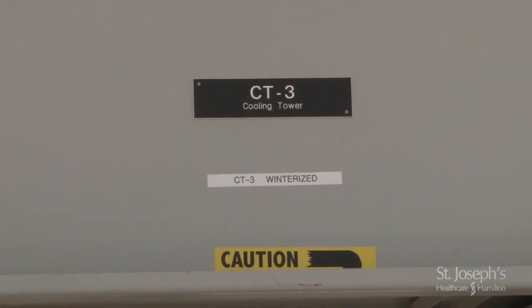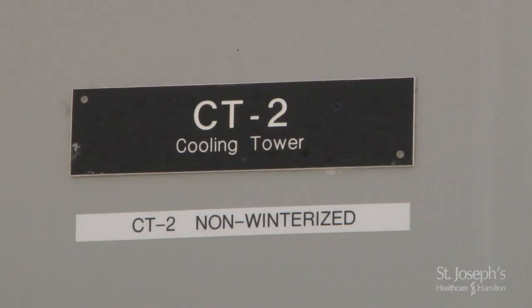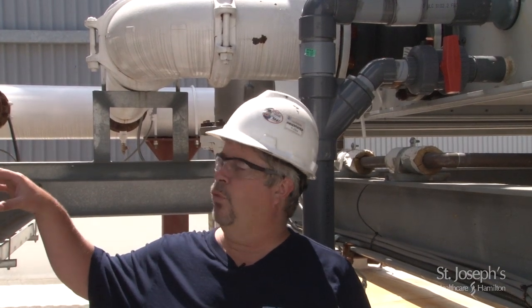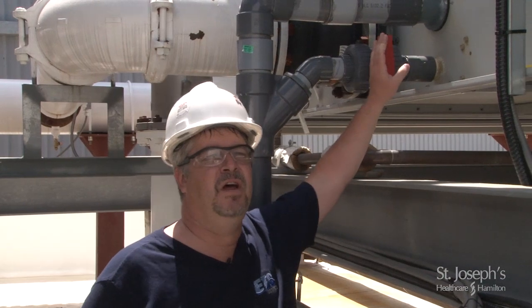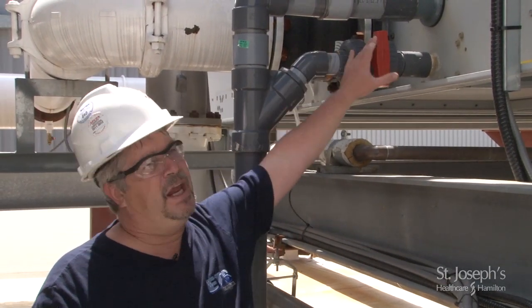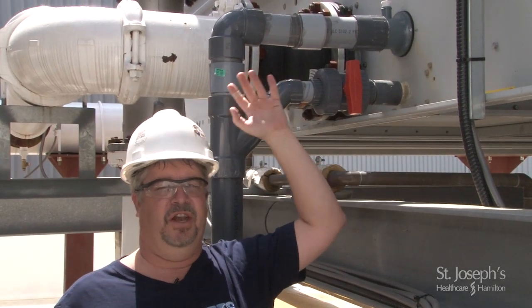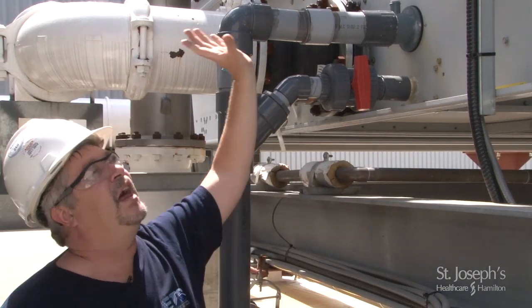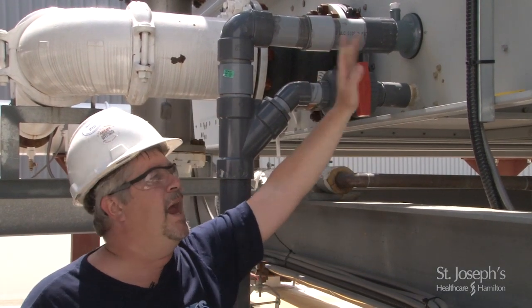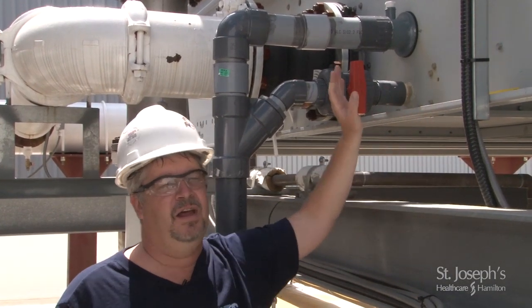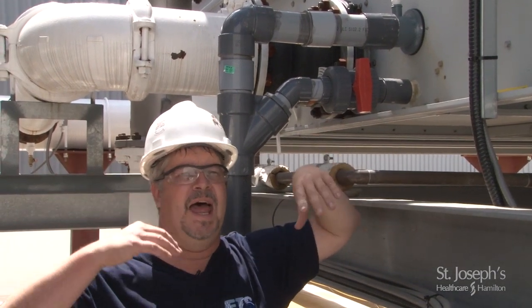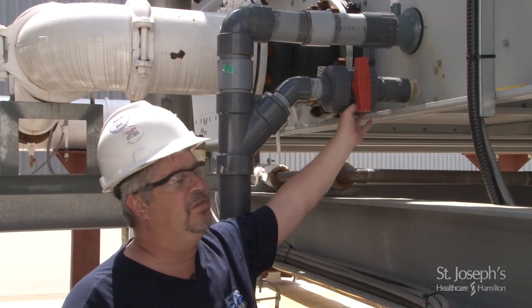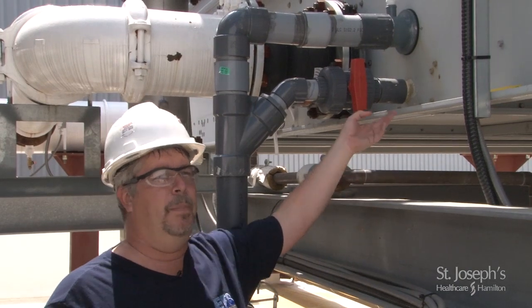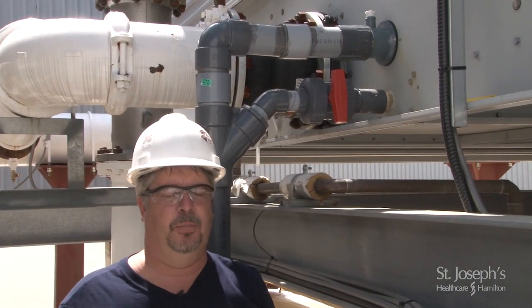Some of the towers are meant for winter operation, and some are strictly summer operation, which means in the winter they will be shut down, isolated, and drained. And when you do that, again, you'll be opening your drain valve and allowing the water to drain out of the basin. Once it's drained through the winter, if the tower is not going to operate, leave your drain valve open, because over the course of the winter you are going to get snow, rain, and sleet. That can access through the fan port at the top of the cooling tower, and it will accumulate within the basin. If you leave it closed, that will start to build up, and then you're freezing and cooling, freezing and cooling. So if you just leave the valve open, anything that does accumulate in there will, by attrition, just drain itself out of the tower until you're ready to put it back online.